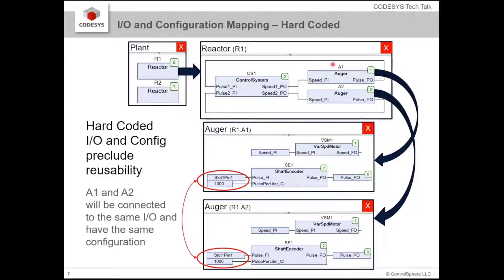Unfortunately in this kind of system, if we were to hard-code these, they would be permanent — this auger would be connected to that IO and this auger to this IO. The only way we could make this work is to make a copy of this auger — four copies, because there are two augers in each reactor. We'd have to make copies and hard-code that information into each copy. Now we've got duplicate code, which is something you'd never want, and the object is no longer reusable.